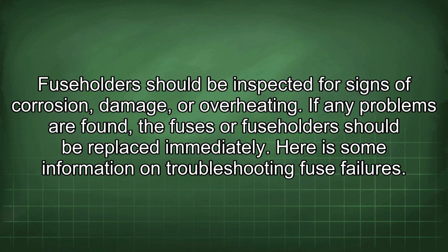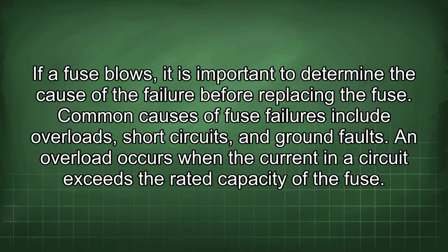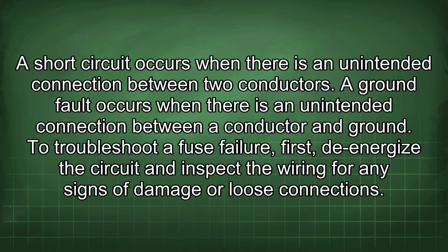Here is some information on troubleshooting fuse failures. If a fuse blows, it is important to determine the cause of the failure before replacing the fuse. Common causes of fuse failures include overloads, short circuits, and ground faults. An overload occurs when the current in a circuit exceeds the rated capacity of the fuse. A short circuit occurs when there is an unintended connection between two conductors. A ground fault occurs when there is an unintended connection between a conductor and ground.